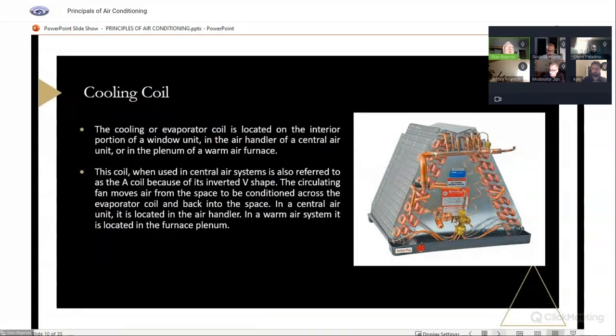So the cooling coil or evaporator coil is located in the space. With a window unit, it's the inside portion, in the air handler of a central air unit, or in the plenum of a warm air furnace. The coil, when used in the central air system, is also referred to as the A coil because of its inverted V shape. So if you see right here, it looks like a V upside down. They call it an A coil.